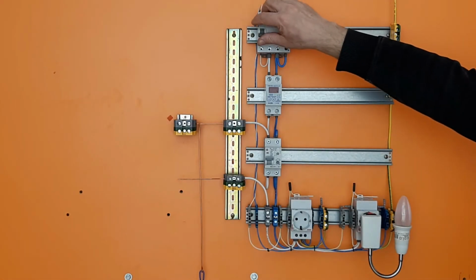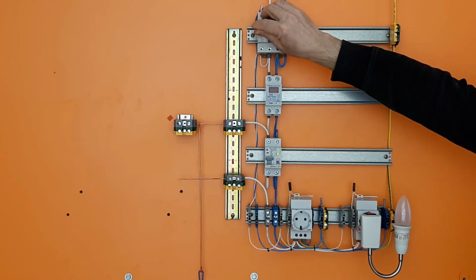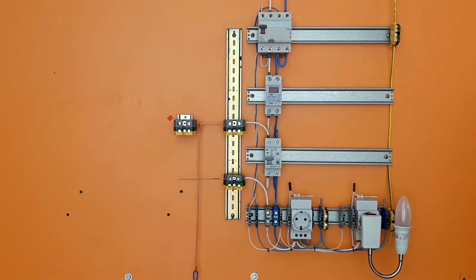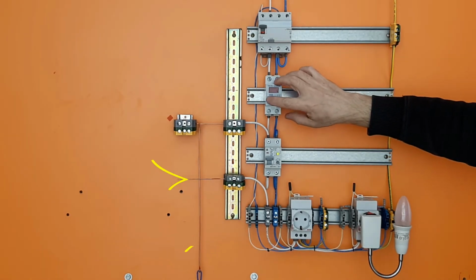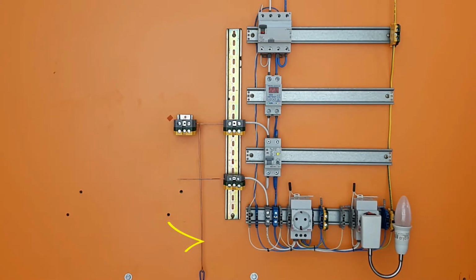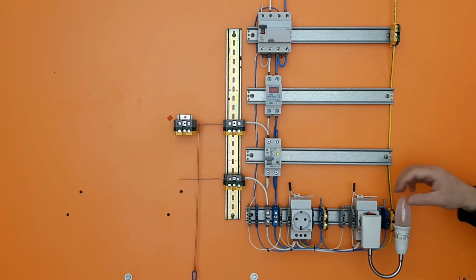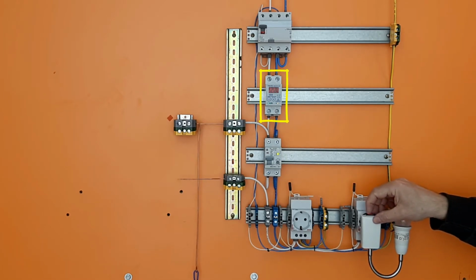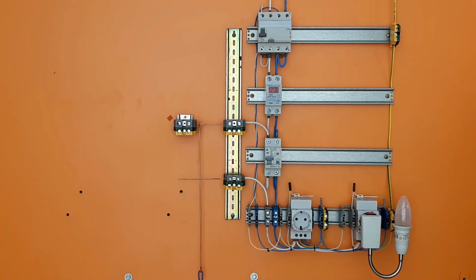The following experiment simulates a connection failure due to the sliding contact of the conductors. The slide itself will be obtained using electrodes, one of which will be stationary and the second one to be part of the pendulum. For comparison, let's add an AFDD arc fault detection device. The voltage relay is used here only for monitoring power indicators. Immediately after switching on the load, our device worked and the AFDD didn't notice anything.